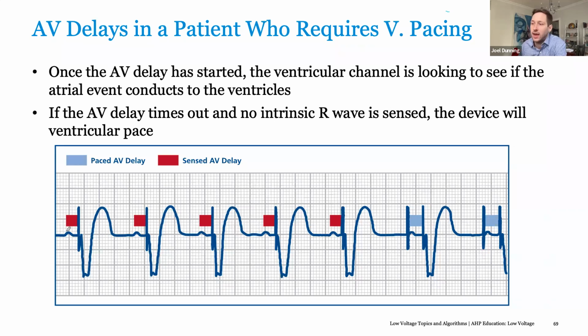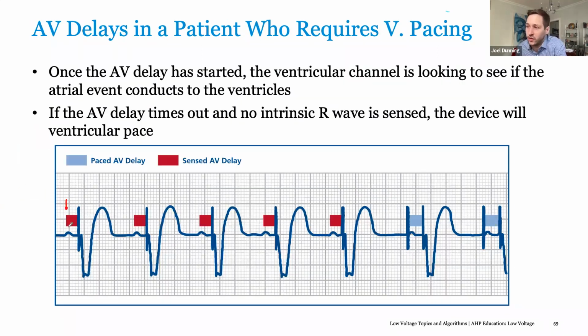In this case, we have an atrial sensed event occurring here, which starts our AV delay. If you remember, our sensed AV delay in this case was 150 milliseconds, so we'll call it 150. I'm not going to count out the boxes here. It waits its full 150. No ventricular event occurs, so it paces.